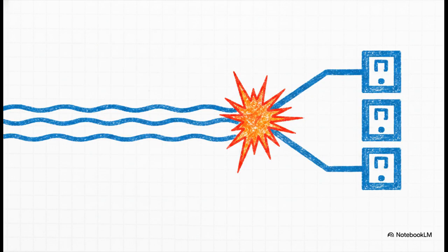And you know, it's not just the phase angle you have to worry about. Matching the phase sequence is just as critical. Imagine your generator is pushing phases A, B, C, but the grid is expecting B, A, C. Even if your voltage and frequency are a perfect match, closing a breaker on a reversed sequence effectively swaps the phases and triggers the exact same type of explosive, catastrophic failure as a mismatched vector group.